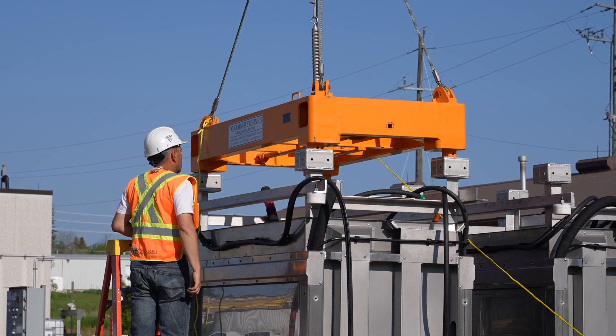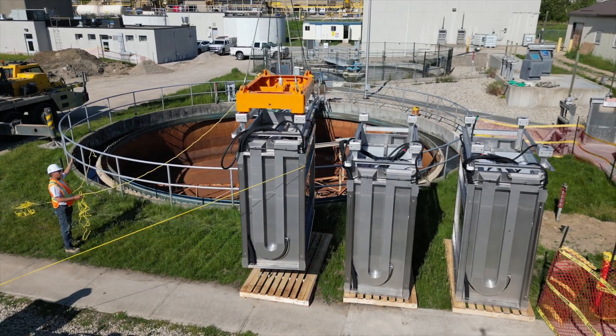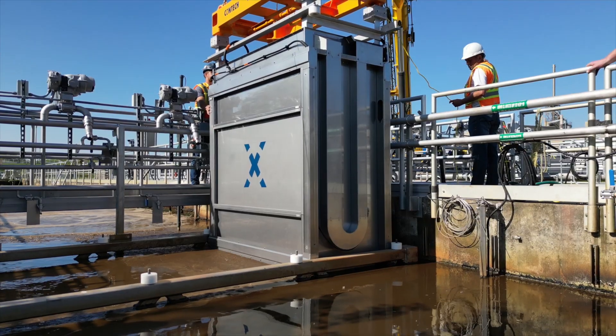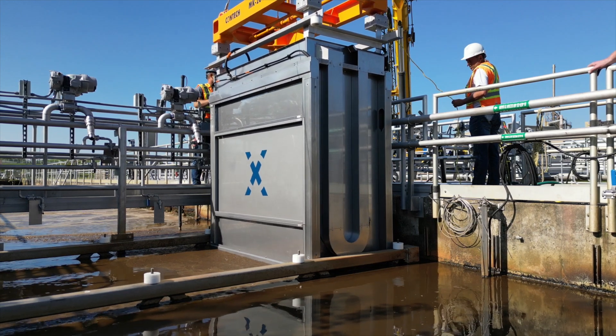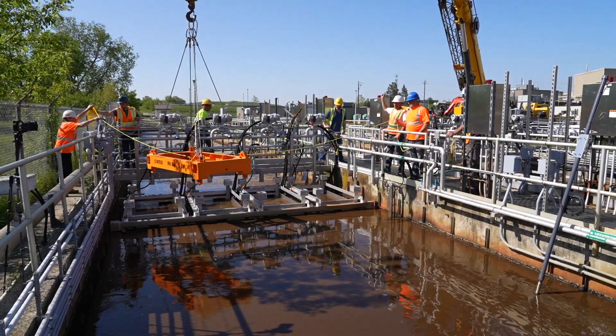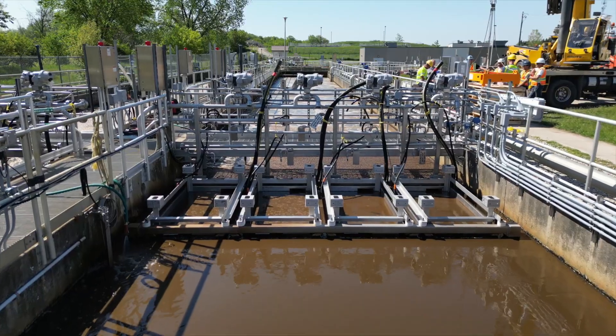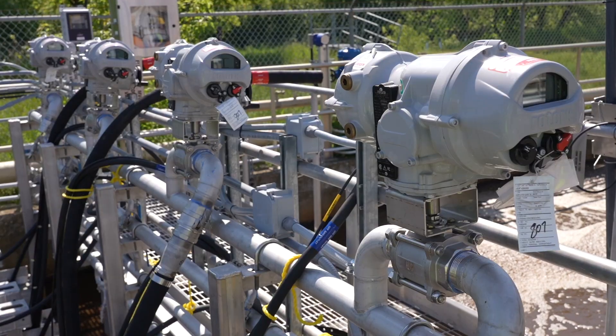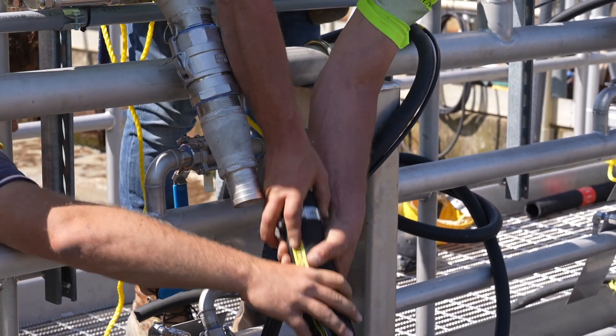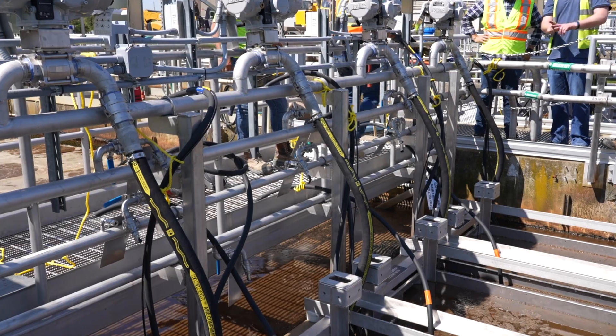The rig gets lifted on top of the module and locks automatically into place by the crane. The crane lifts it and locks it into position. Once you fly it over and set it into the tank, no one has to enter the water to unhook it — it automatically disconnects and releases, and you can lift it out with the crane. The connections from the modules to the air piping system are all done by rubber hoses and cam locks, making installation very quick, easy, and flexible, and taking any vibration concerns away from the system.